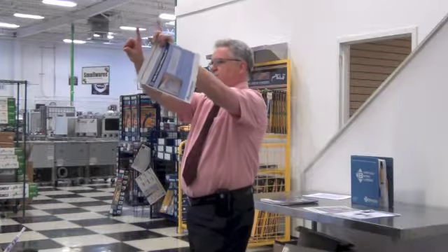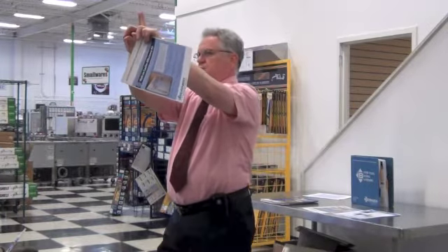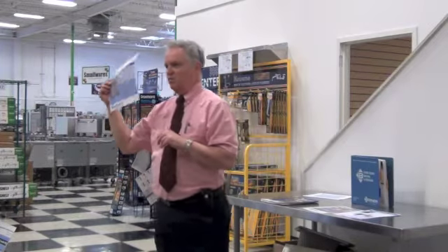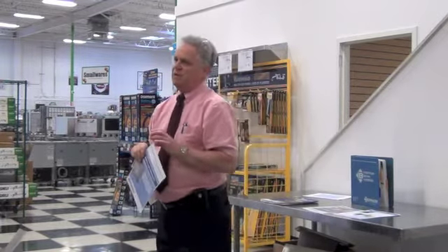Everybody know what a magnetic reed switch is? You have 2 magnets. They touch together. When you separate the door, the magnets pull apart and the unit turns on. Please do not do this on a freezer, okay? It's not designed for that. Only for the coolers where the temperature is above that freezing level and the humidity is not an issue.